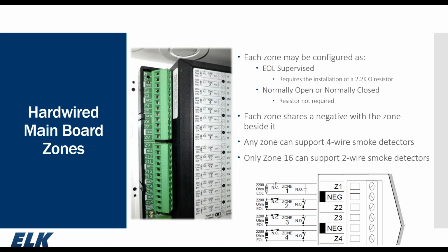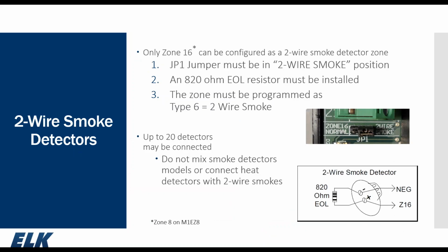Any zone on an M1 system will support 4-wire smoke detectors, 12-volt DC, 4-wire smokes, the main board as well as our hardwired input expanders. You can connect your 4-wire smokes to them. Only zone 16 will support a 2-wire smoke loop. Those detectors must be listed on page 6 of the installation manual to make sure that they are compatible with an M1 system. So if ever in doubt, refer to page 6 for compatibility for 2-wire smokes. They do require a different resistor. It's an 820 ohm. There's a special jumper right below zone 16 called JP1, which selects between normal versus 2-wire.